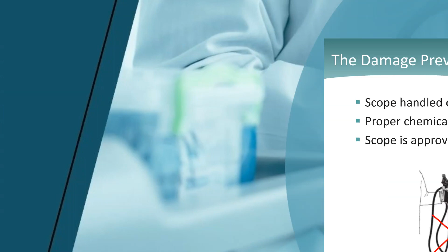Now, as we move the scope from the manual clean into the AER, we want to make sure that we're handling it correctly. We're not bunching it up into one hand, we're carrying it with the distal tip separated from that light guide connector, and we're holding it with two hands with no sharp angles. We want to make sure that we're loading and unloading it correctly, because a lot of the same principles that we talked about in the transportation section still apply to this loading and unloading in the AER. So there's a lot of opportunity here for the prevention of damage just by simply making sure that we're doing it properly.